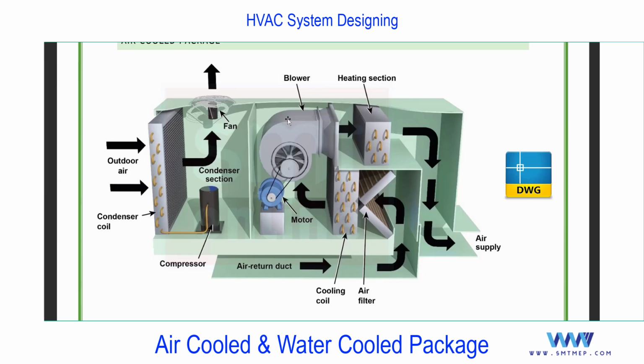degrees centigrade. If the outside temperature is above 35 degrees centigrade, like 45 or 50, like in the Gulf, in that case water cooled system efficiency is higher, because if the outside temperature is higher and you use the air to cool the condenser, the difference of the temperature is less, na? So the efficiency of that air cooled system drops. In that case, water cooled system works efficiently with a small size capacity system.